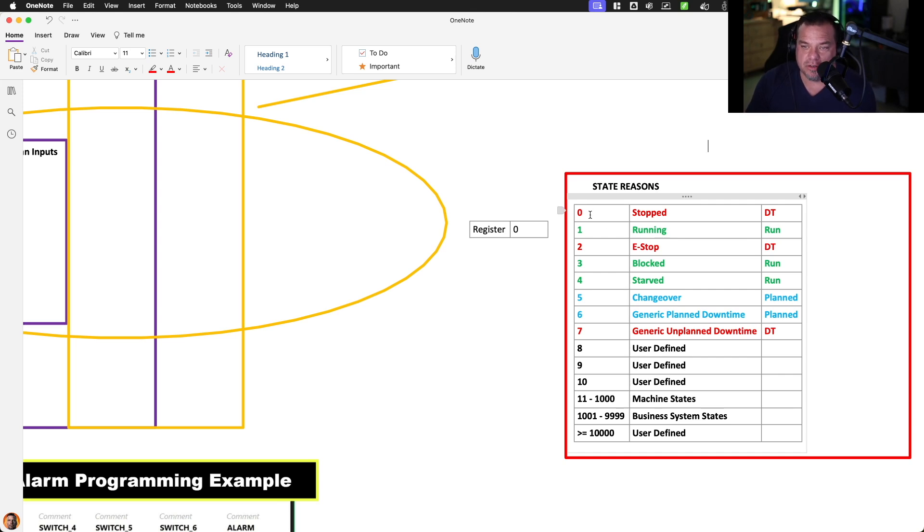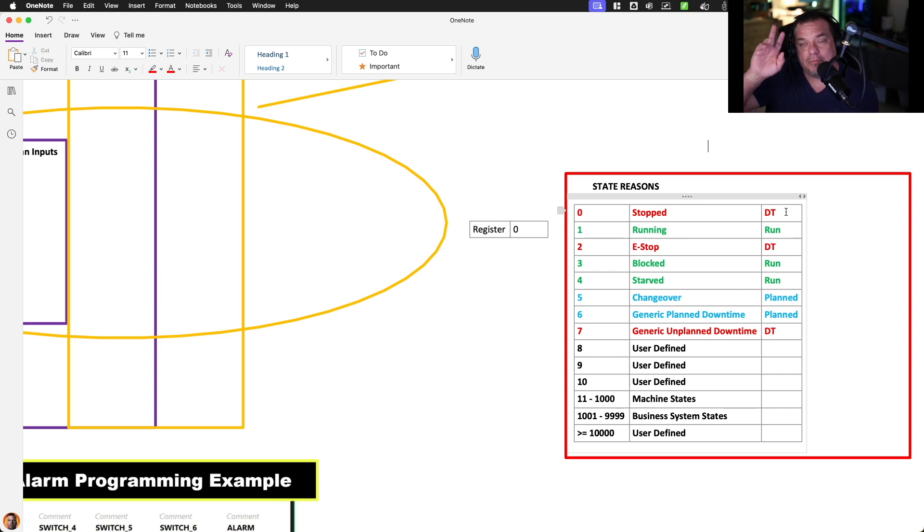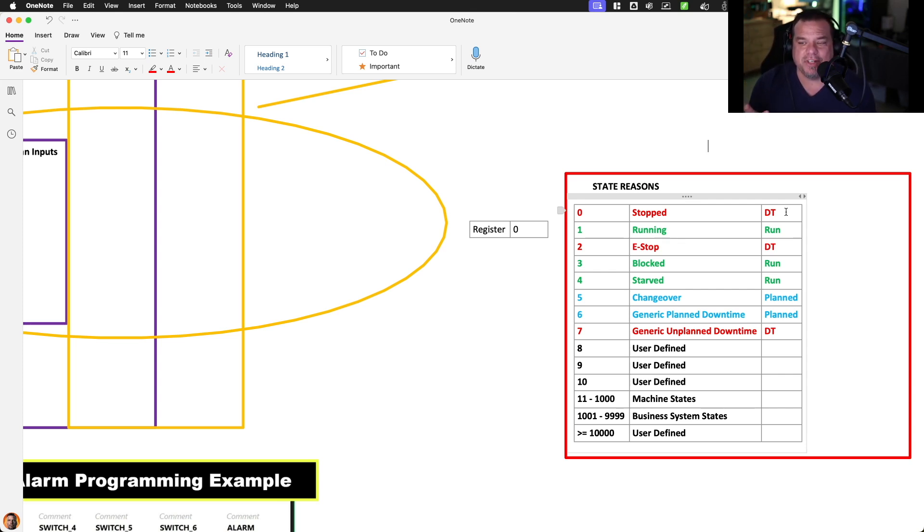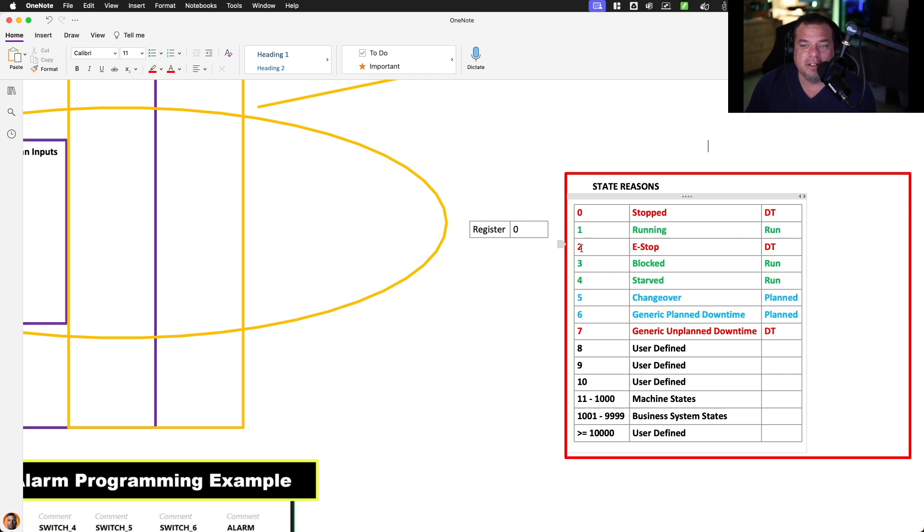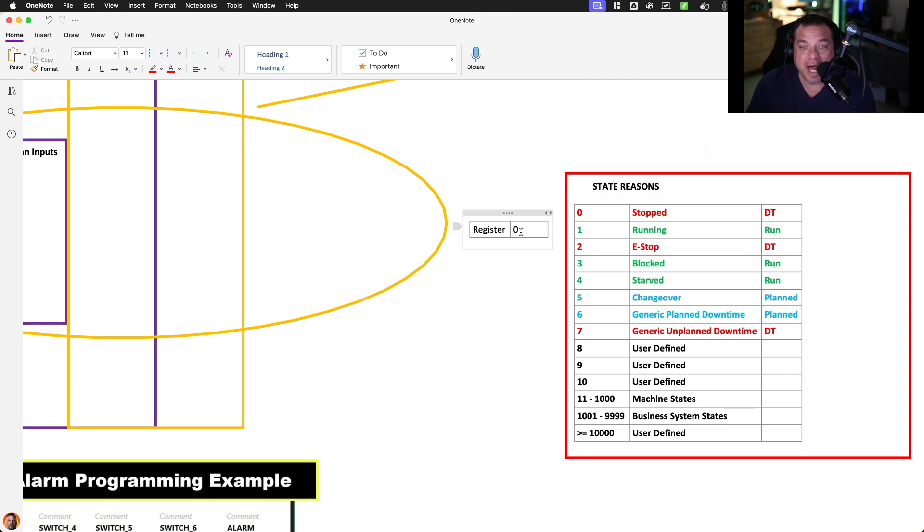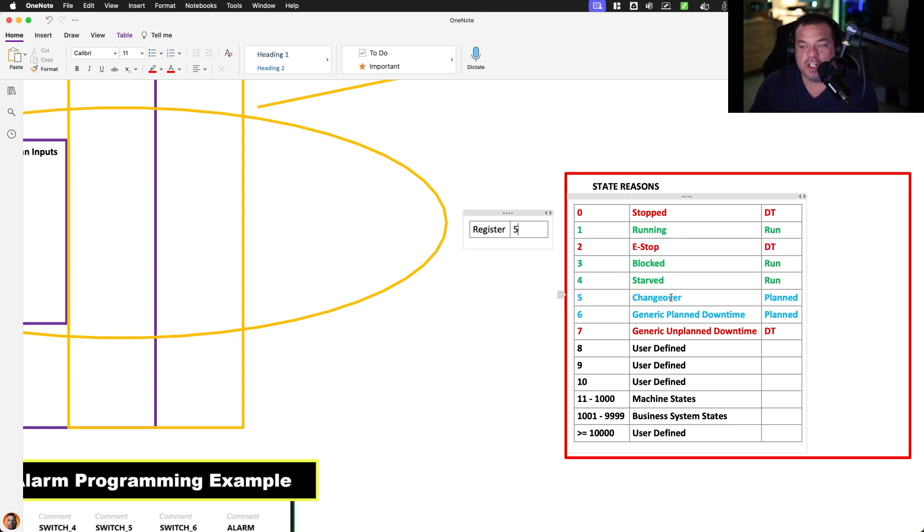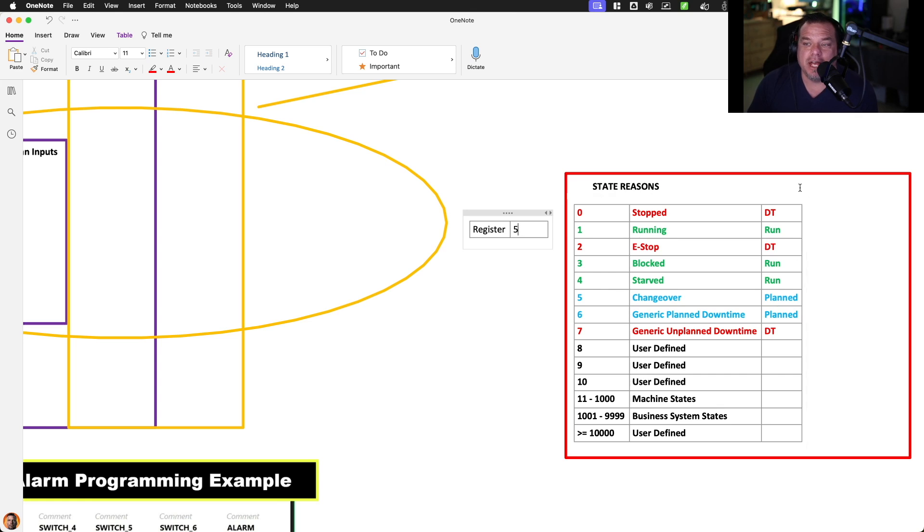So for example, we can say zero means that it's stopped. However, we want to say that the mode or the configuration in this case or the classification is that is downtime. If zero, then it means we're in downtime. If one, it means we're running. If two, when we see a physical e-stop, we want to categorize that as downtime. If we see five, then we want to say that that's in changeover mode and we're going to say that's planned downtime. And this is for generating our KPIs.